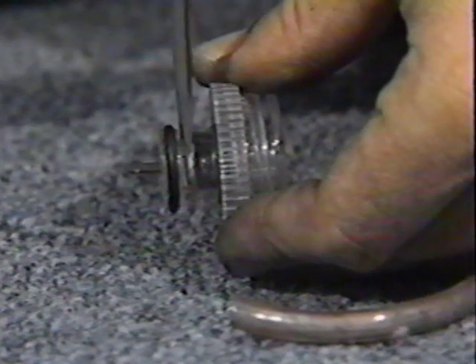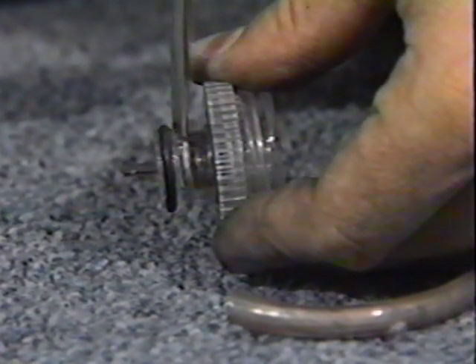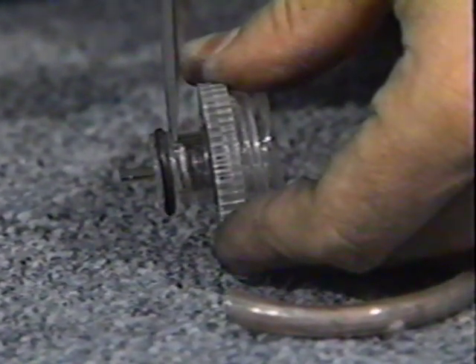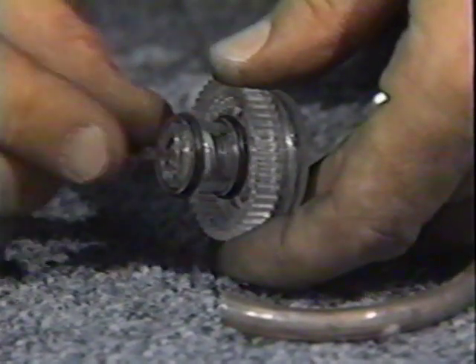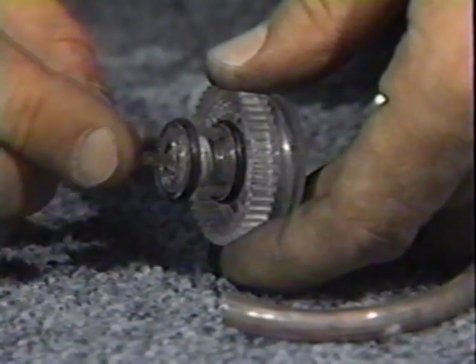Now disassemble the control valve and apply petroleum jelly lubricant to the black O-rings. Inspect the donut O-rings inside the barrel. If cracking exists, the control valve must be replaced. Also, inspect the piston travel to assure that it is not sticking and operates smoothly.